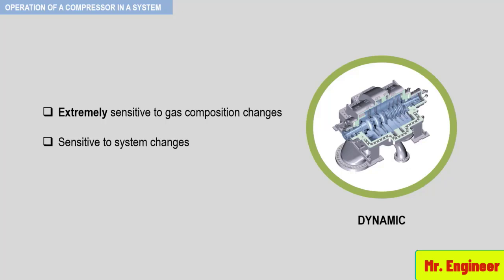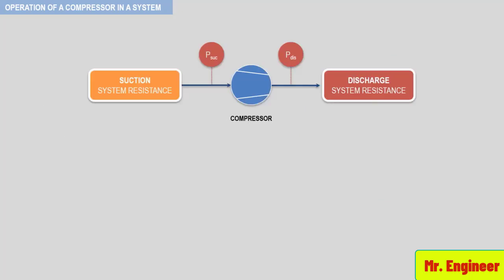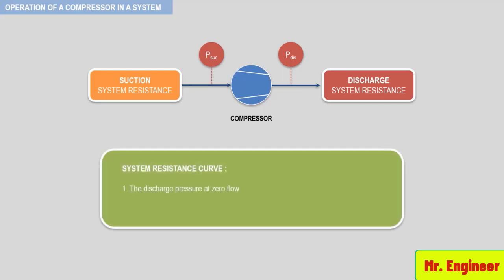One additional point is that the process system characteristic curve can also change. The system resistance curve, which represents the head required by the process, is a result of the terminal pressure at zero flow and the system resistance as the flow changes. A recycle loop, for instance, is comprised of friction loss only and will have a relatively steep system resistance curve. On the other hand, an instrument air compressor pumping into a receiver vessel with a relatively small system resistance will have a system resistance curve that approaches a horizontal line. The combination of a flat dynamic compressor curve and a flat system resistance curve can lead to a very unstable situation. Remember that the operating point is determined by the intersection of the compressor and system resistance curves.